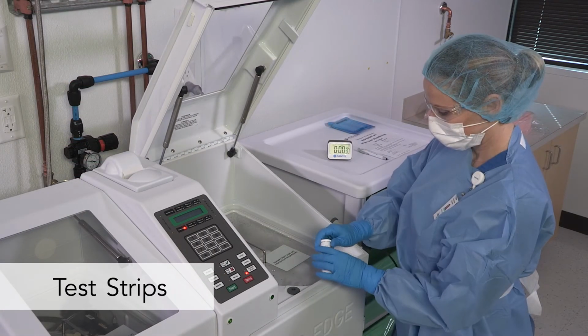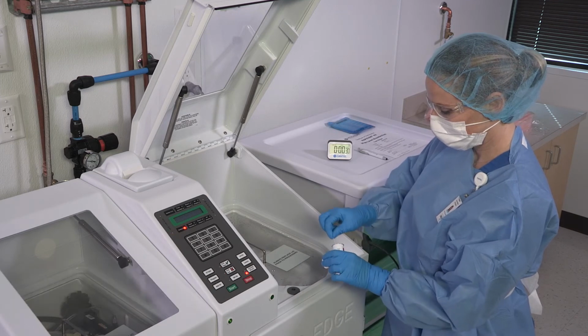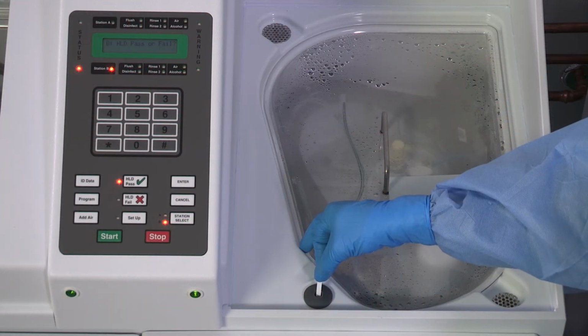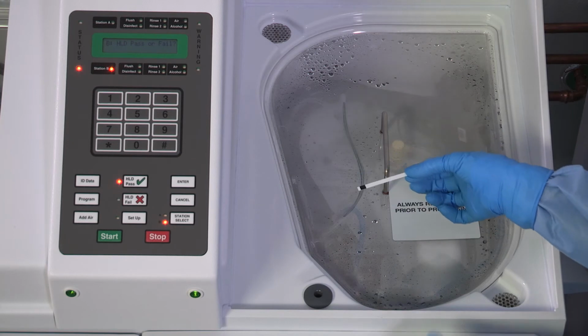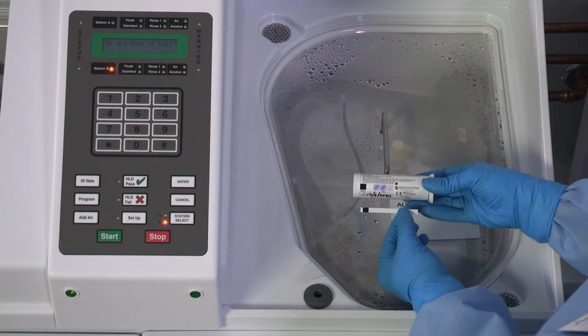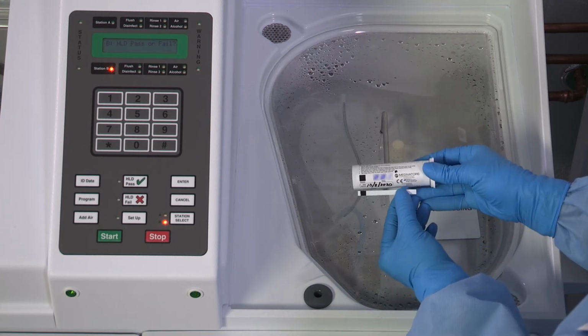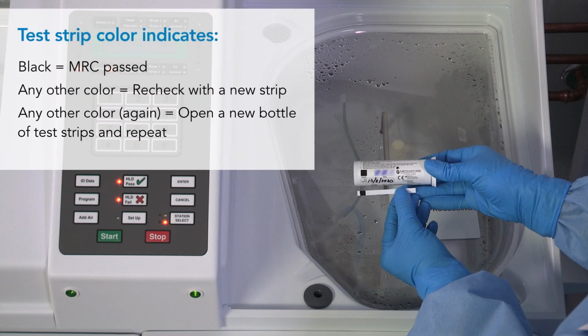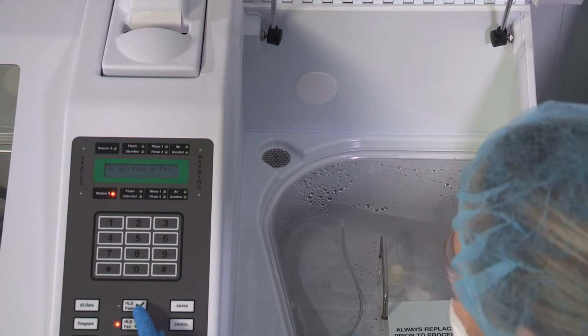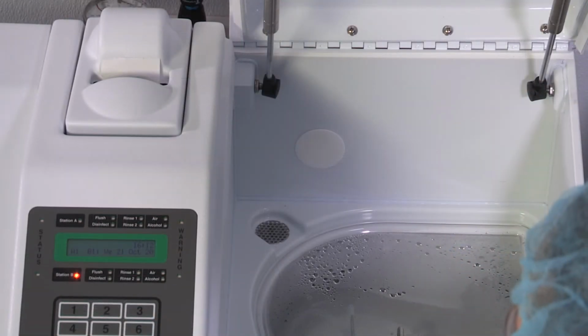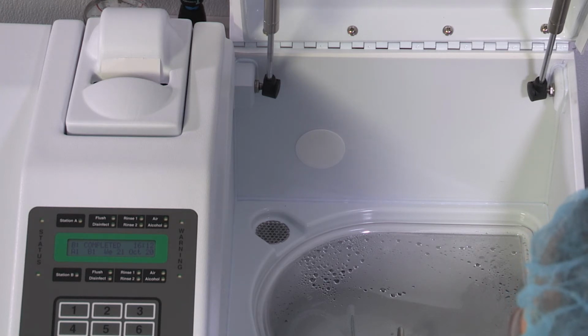Open the station lid. Dip a Rapicide PA test strip into the disinfectant sample port located near the front left corner of the basin. Compare the results to the chart provided on the test strip bottle. Do one of the following. If the test strip color indicates the disinfectant MRC was met for the cycle, press HLD Pass on the control panel. After 10 seconds, the process indicator light illuminates and completed displays on the screen.